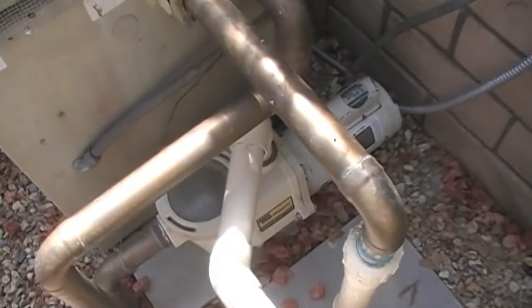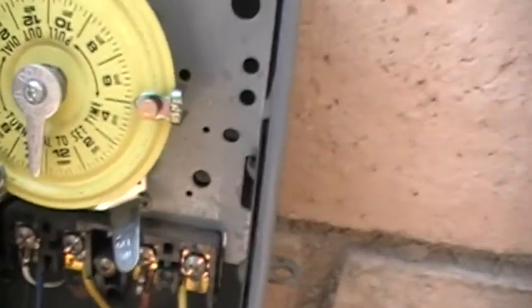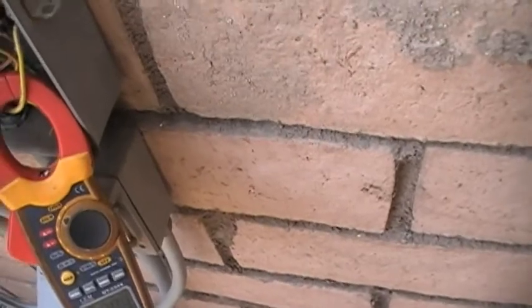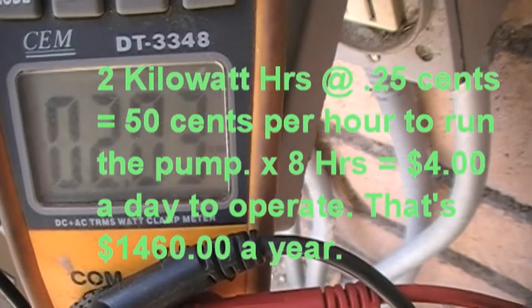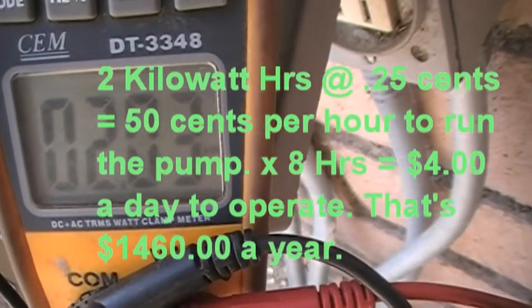Then we'll put in the new pump and see what it's using. The time clock is set to run nine o'clock in the morning until five in the afternoon — that's eight hours a day, which is pretty typical. Let's go ahead and get a kilowatt reading on this thing. We are at 2.02 — that's two kilowatt hours, or 2,020 watts. Just remember that number.